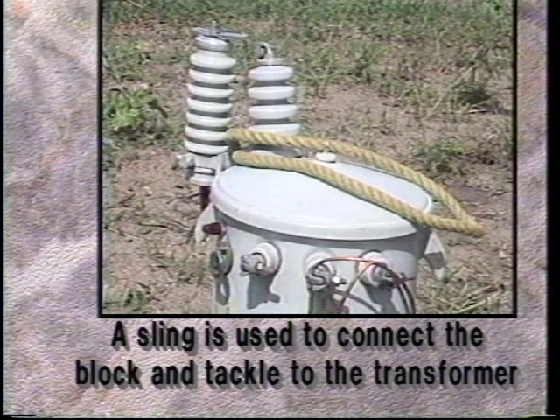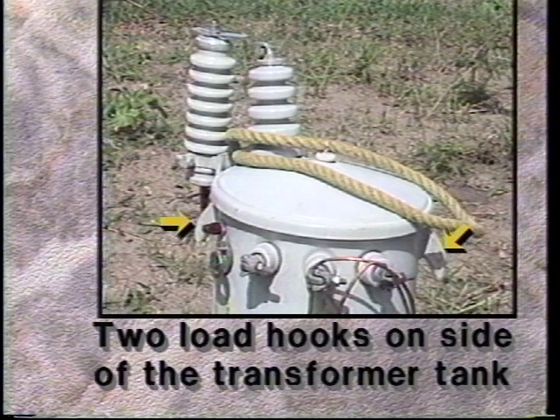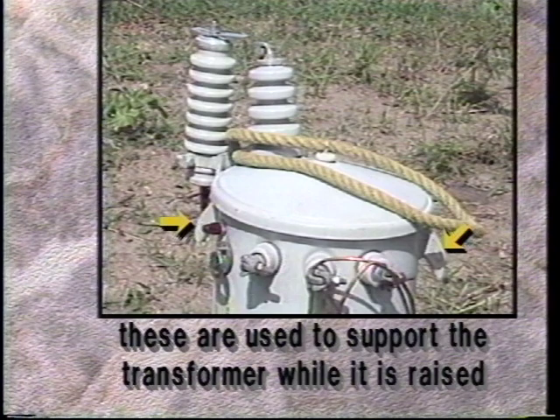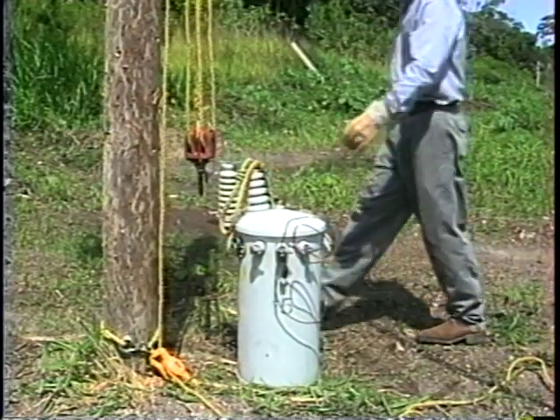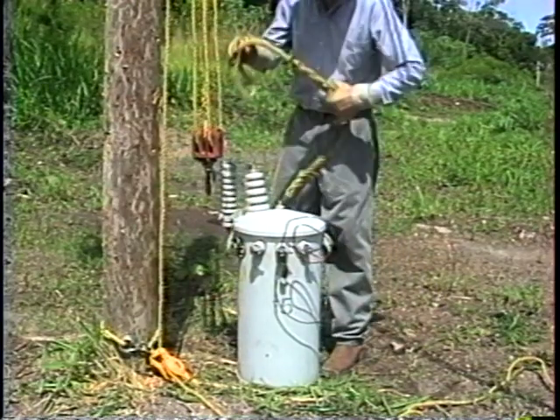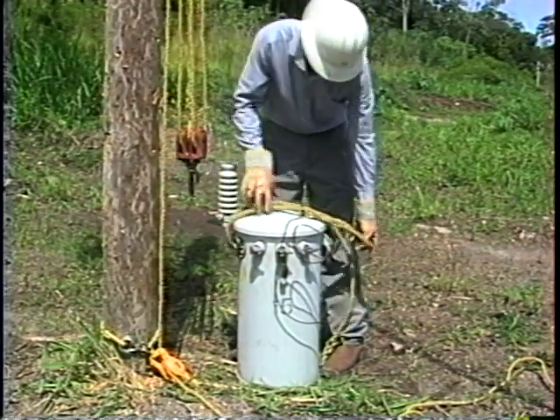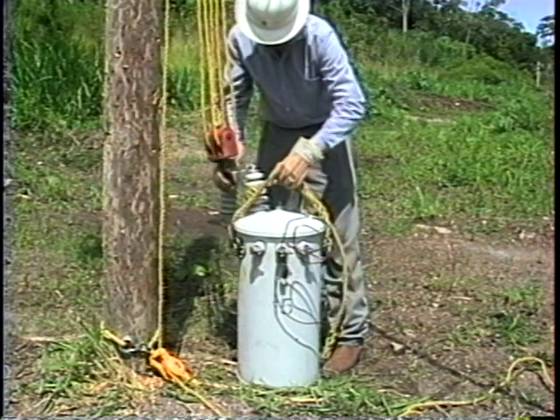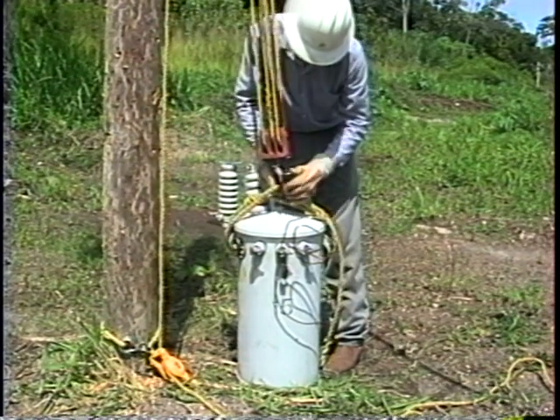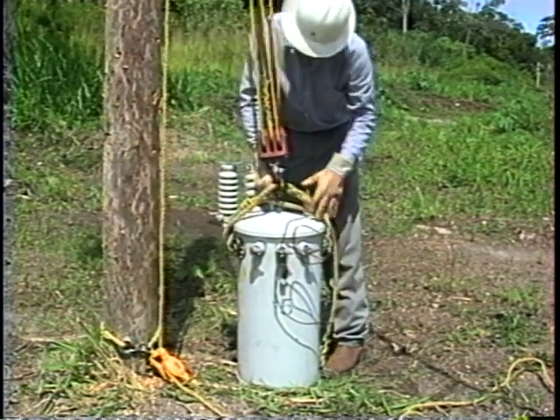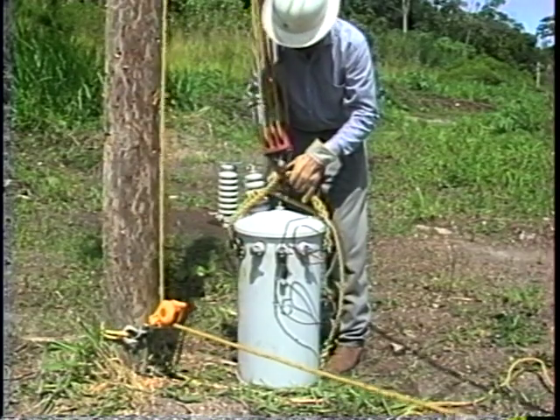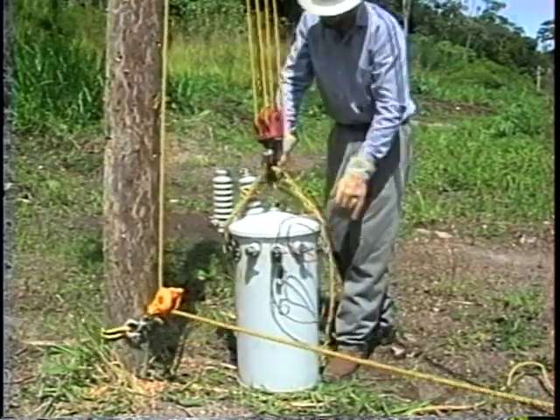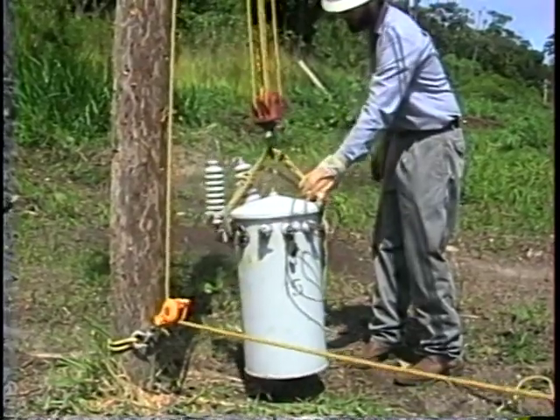A sling is used to connect the block and tackle to the transformer. There are two load hooks on the side of the transformer tank. These are used to support the transformer while it is raised. The groundman places the sling over these two load hooks, then attaches it to the block and tackle. Tension is applied to the fall line, and the transformer is slowly lifted off the ground.